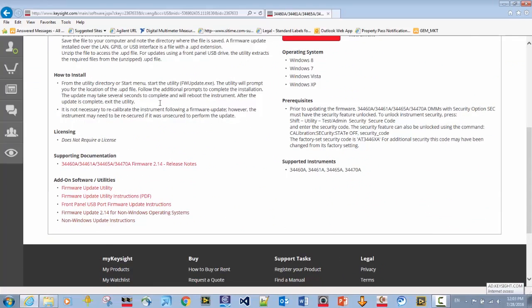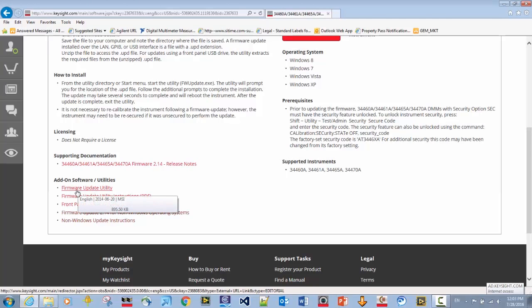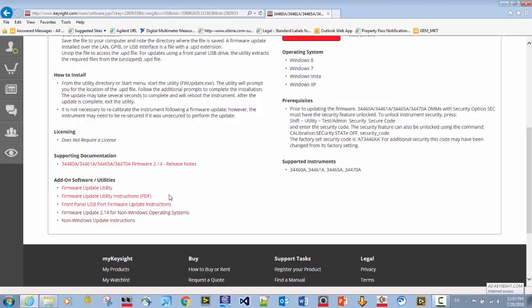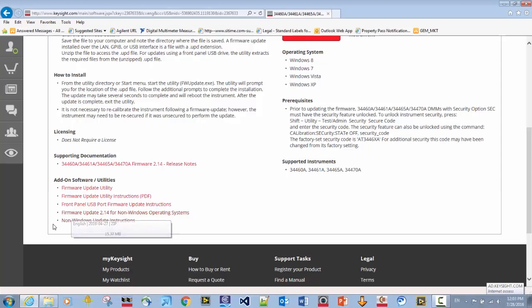I want to draw your attention to the add-on software and utilities. You can see we have the links for the firmware update utility, which is the Windows-based app. We also have instructions for using that if you're going to update the firmware. What we are going to do is show the firmware update without using that, and we do that by selecting the link which says firmware update, in this case 2.14, for non-Windows operating systems.